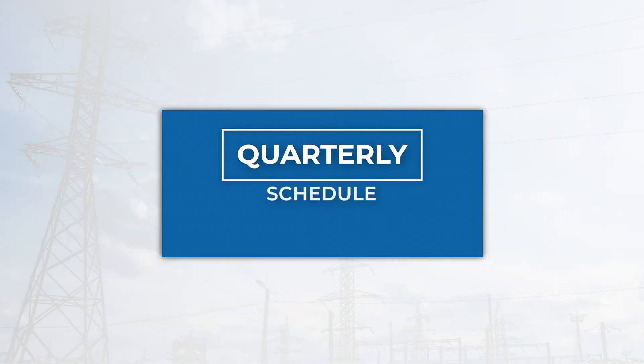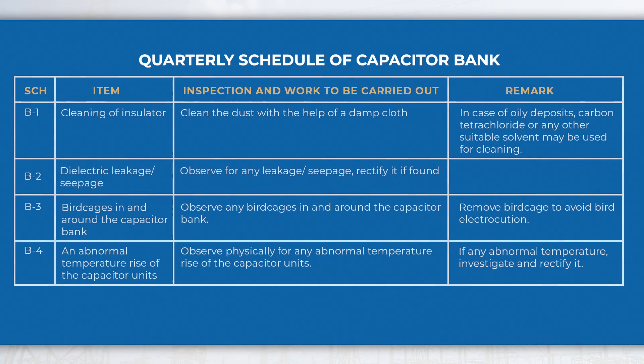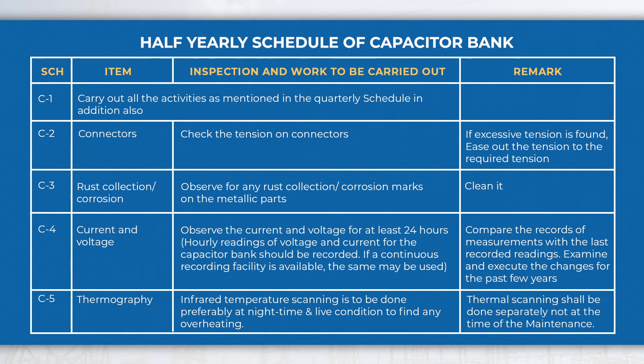In the quarterly schedule of the capacitor bank, perform activities like cleaning, checking for any leakage and bird cages in and around the capacitor bank, etc. In the half-yearly schedule, perform activities like checking tension on connectors, observing the current and voltage for at least 24 hours, thermography, etc., in addition to quarterly schedule activities.